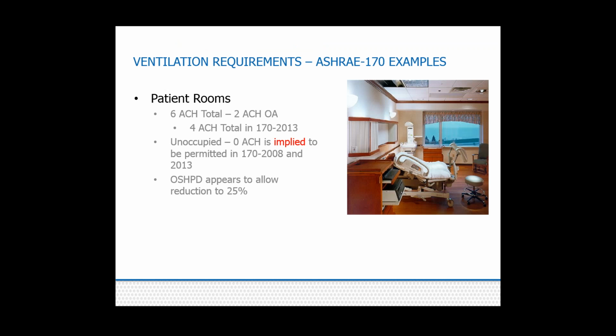So I'm going to do a couple of examples out of ASHRAE 170. For example, in a patient room, the requirement in 170-2008 is for 6 air changes total and 2 air changes of outside air. One thing I want to clarify about that in standard 170, which is different than a standard like 62.1, is that in standard 170, you can add up the outside air requirements for each room, total them, and if you bring that much in at the air handler, you're good. So just because a patient room requires 6 total air changes and 2 air changes of outside air, this does not mean your air handler has to be at least 33% outside air. I sometimes call that the California rule because the rest of us have to deal with 62.1 and the multiple spaces equations, whereas the lucky dogs in California can just add up the outside air and bring it in at the air handler.